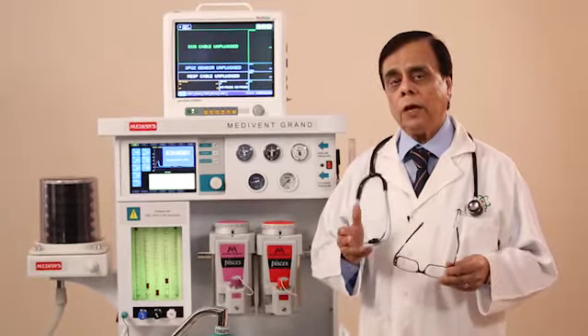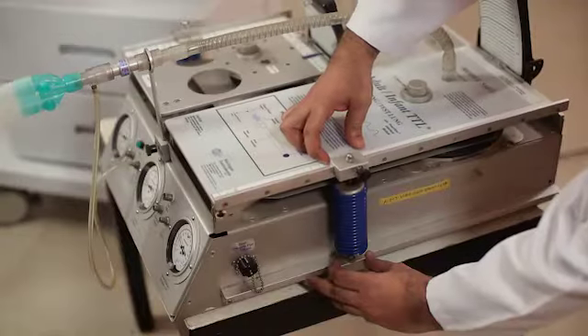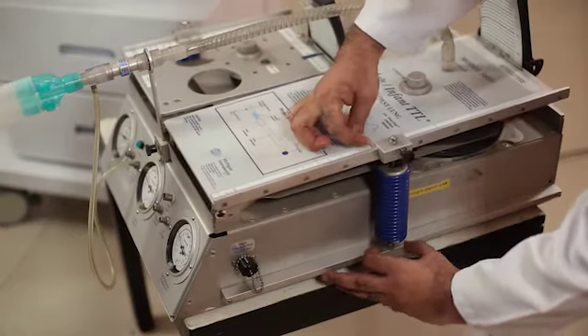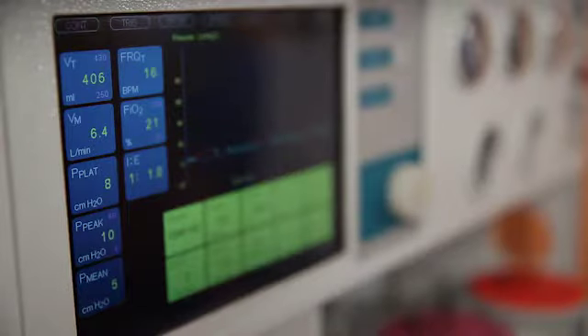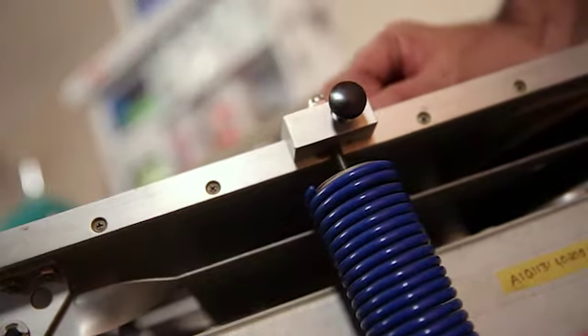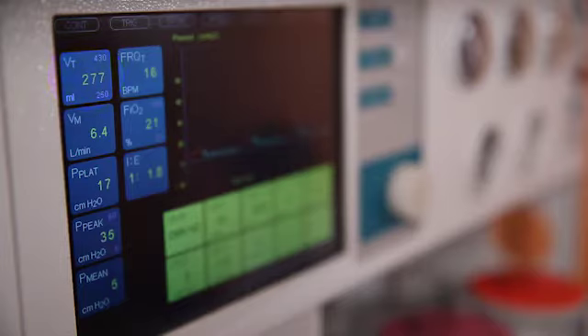And second is the capability. The main thing we are doing is giving a ventilator which is equivalent to any critical care ventilator available today. The machine has several safety devices. One of them is breath-to-breath correction. What we mean by that is that if the compliance of the patient goes down for some reason, the machine will automatically try to correct it and bring back the normal tidal volume that we have set. And this is a great blessing in patients who may develop pulmonary edema, or who may develop bronchospasm during anesthesia.